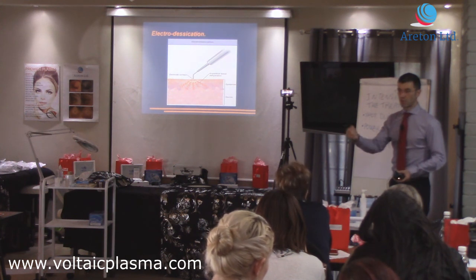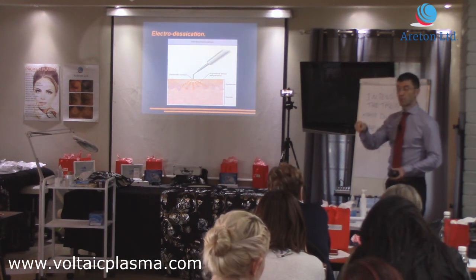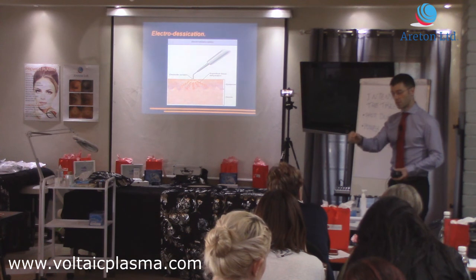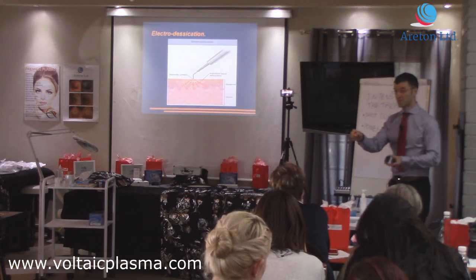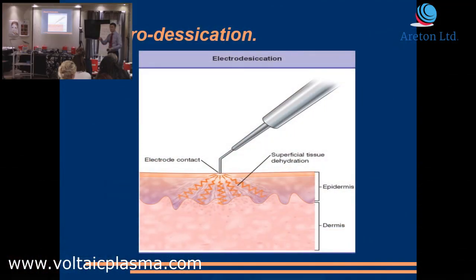And then you want to know that in that spot you put the arc on for 400 milliseconds. So you put it for 200 milliseconds. If you want to make sure that it's going to be there for 400 milliseconds, then the new device is going to tell you, okay, I only counted 200 milliseconds, I need another 200 milliseconds there. It waits for you to release another 200 milliseconds of arc at that point. And once it has counted a total of 400 milliseconds, it stops operation. Do you understand? Sort of.